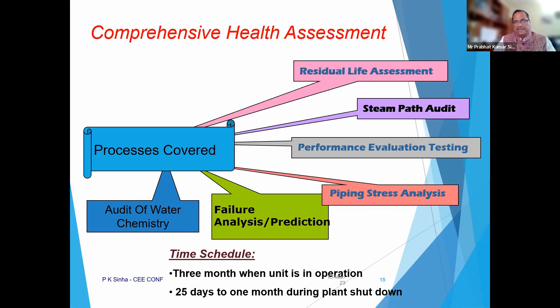Go for residual life assessment, which gives you the aging and the state of what the plant equipment is running. Then, in order to assess the turbine, go for a steam path audit. Then performance evaluation test, which entails everything about the power plant's performance. Then the piping, another area where losses occur. So the entire power plant can be mapped across these six areas through techniques like residual life assessment, audits, performance assessment, and water audit, which directly affect the life of the plant. A very good menu card can be developed, giving actionable points for the plant's maintenance and upgradation in the coming days.